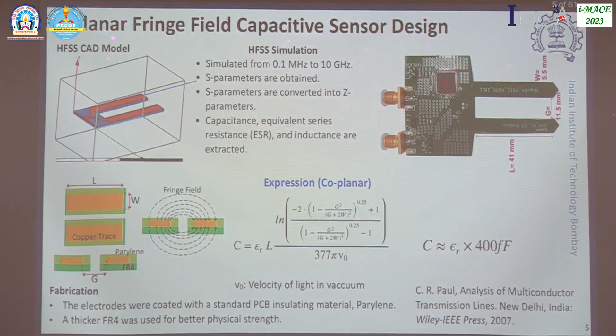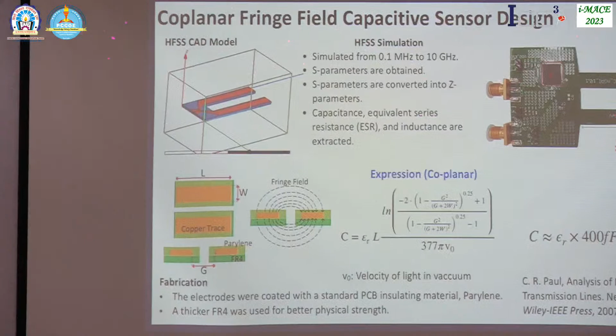There are pros and cons. For example, if you reduce the gap too much, then you don't get enough information about the material between the two probes. Electric field lines will cover only a very small number of molecules when they start from one plate and go to the other, and therefore you will not get the proper effective average dielectric constant, because soil is not a uniform, homogeneous material. It's actually a complex mixture. If you collect a sample from agricultural land in Pune, and then from agricultural land in Nagpur, and then go, for example, to Karnataka, the characteristics change, even for a given soil moisture content. So it is completely dependent on geographical location, and we need to keep enough volume to be covered.